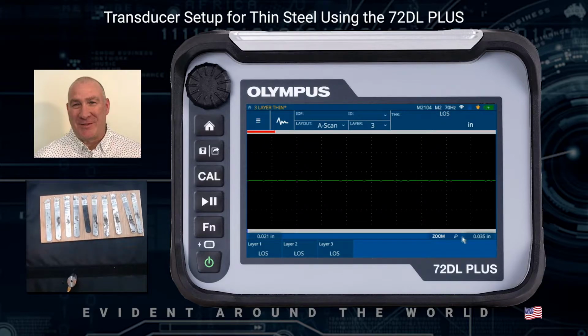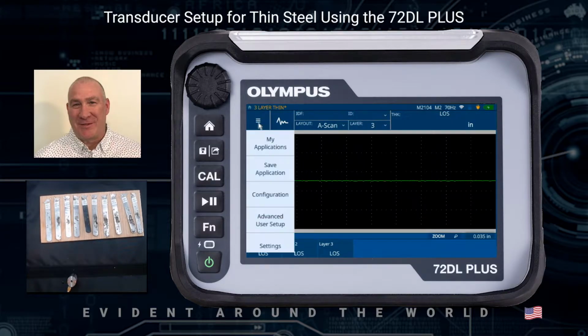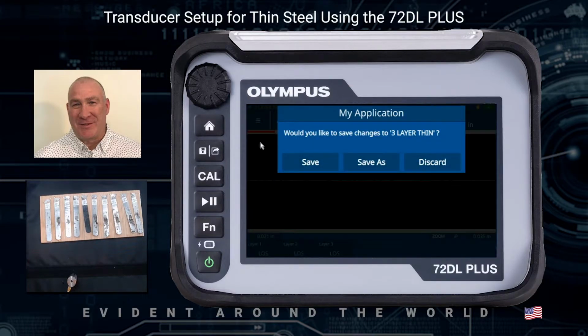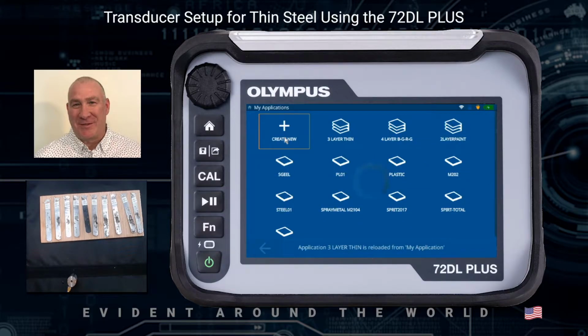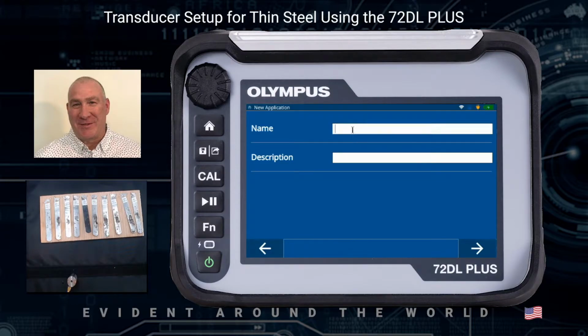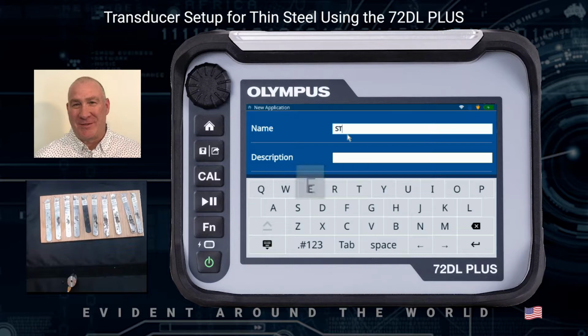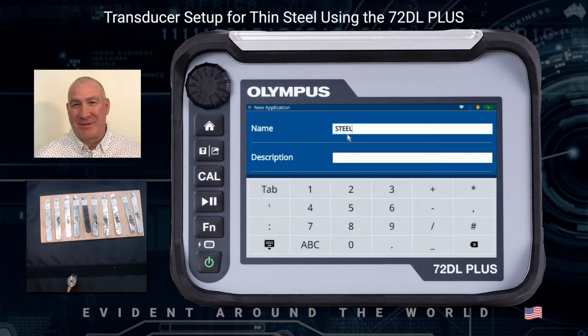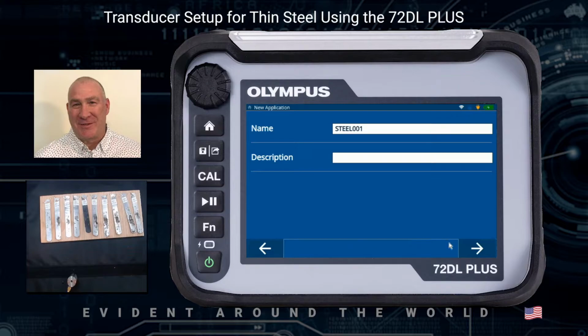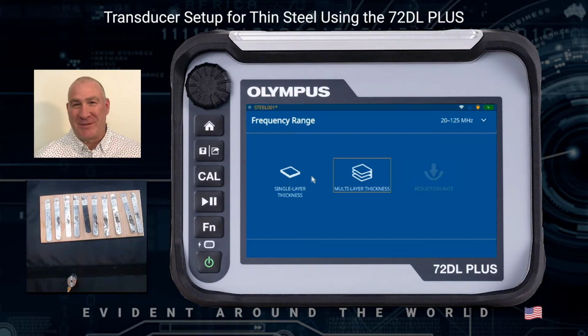First thing we want to do is click on the burger menu, click on My Applications, and I'm going to disregard what I was working with, and create a new application and give it a name. In this case, I'm just going to call it STEEL 001. I'm going to close the keyboard and go to the next arrow key. This is a single layer application, so I also want to select what frequency range I'm going to be working with. Since I'm using the 125 megahertz transducer, I'd like to make sure that I'm set to 20 to 125 megahertz, and it's a single layer application.